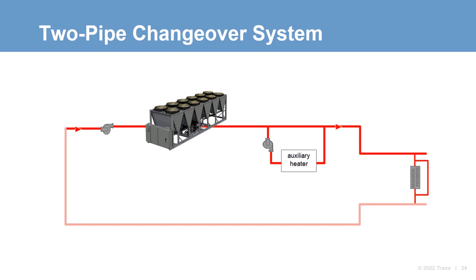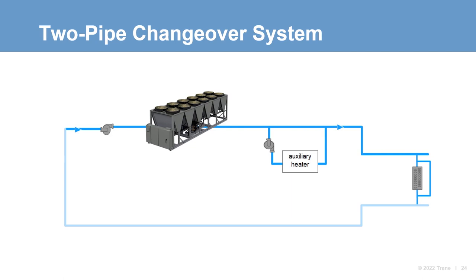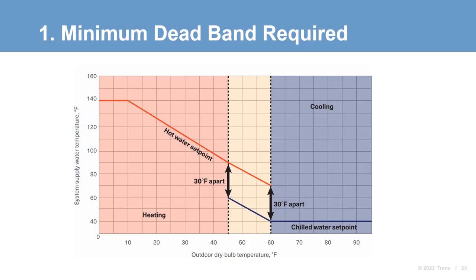With this type of piping distribution, the system will be in either heating or cooling mode. When the heat pump and the system change from one mode to the other, this is called changeover. Because there can be some significant energy implications associated with this changing of modes, 90.1 has several requirements aimed at minimizing excessive energy consumption in these types of systems. First, the system controls must include a deadband between heating and cooling of at least 15 degrees outdoor air temperature. This is intended to limit the system from switching back and forth between modes too often, which can be very energy intensive.